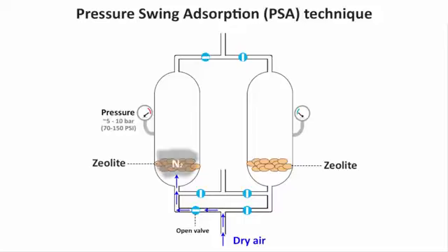Since we don't need nitrogen, the unwanted nitrogen gas is adsorbed by the zeolite during the building of pressure, and it settles at the surface of the tank. When the first tank is almost full, the nitrogen adsorbed in the first tank settles down at the bed of the vessel. Later on, it is released into the atmosphere or captured for other purposes through a valve. While the first tank is adsorbing nitrogen and the pressure is building up, at some point it will get full. When the first tank is full, the pressurized oxygen is collected through an outlet.